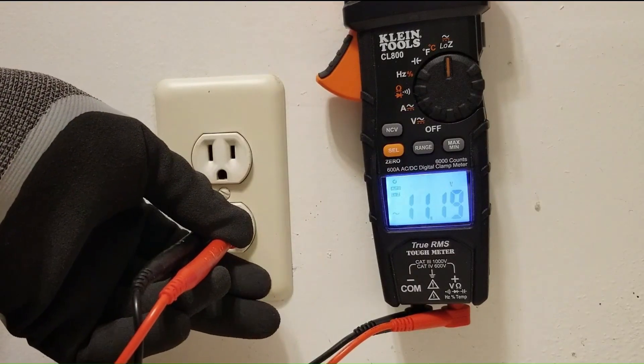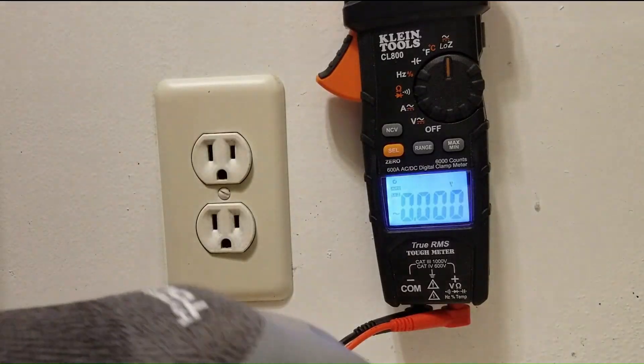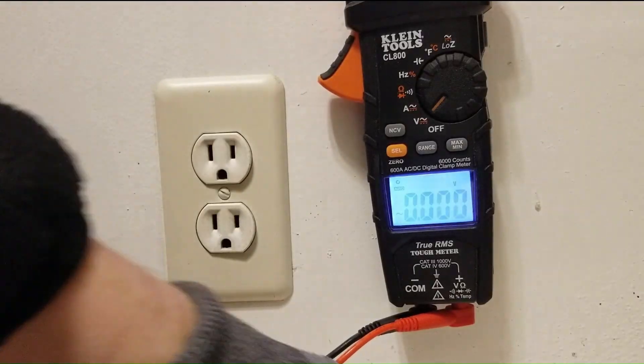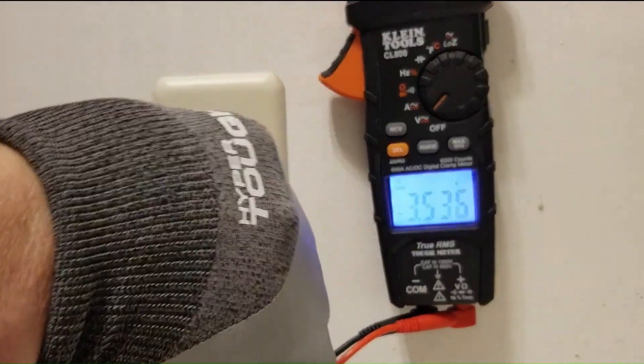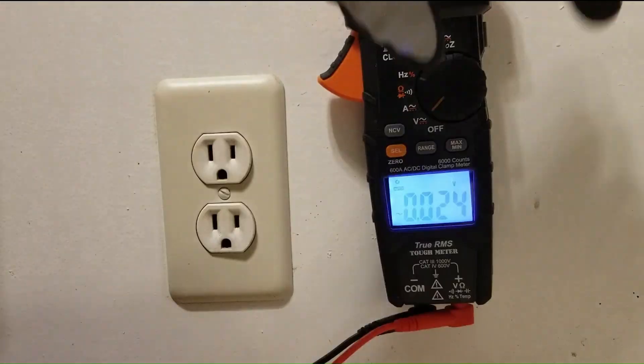So we're using this low Z meter in its low Z mode in combination with its regular mode by plugging the load back in. And that'll tell us that we have a floating neutral. But all we need to know that this outlet is compromised is simply just the low Z mode right there. Low Z tells us we got 11 volts with three kilohm resistance across the outlet. So that's where the beauty of low Z comes in.